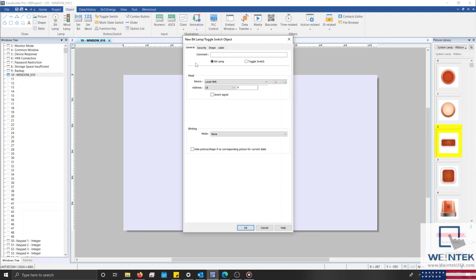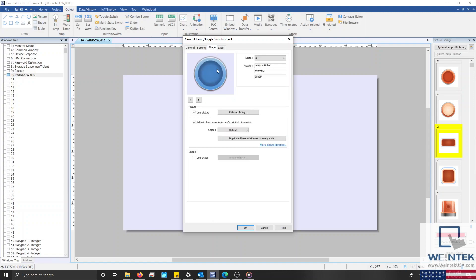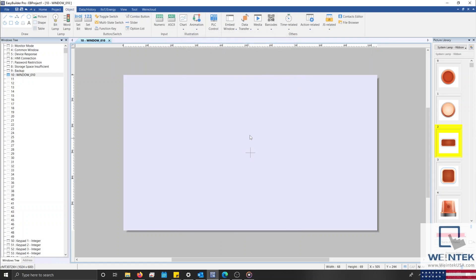Now before I explain the purpose of each tab, I'd like to note that there are a few basic steps that you should follow when creating an object. Step 1 is to define the read or write address of the HMI or PLC that this object will reference. Step 2 is to select the object's picture or shape. Step 3 is to configure the object's font or label settings. And Step 4 is to place this object and define its size.